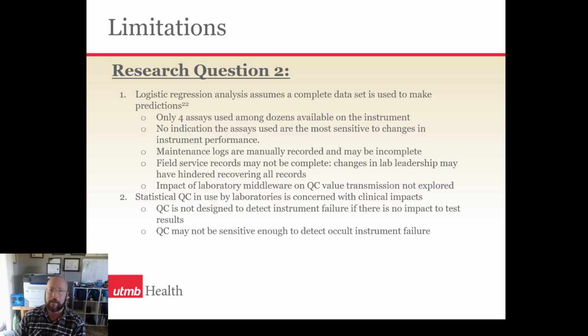Second, statistical QC in the laboratories is concerned with clinical impact, so that statistical QC is not looking for mechanical deviations. You can have an instrument that is mechanically broken and still producing the correct results. But that doesn't mean that that's okay, that the instrument is broken. It just means that the results are okay. So QC is not designed to detect instrument failure as long as there's no impact to test results. QC may not be sensitive enough to detect occult instrument failure.